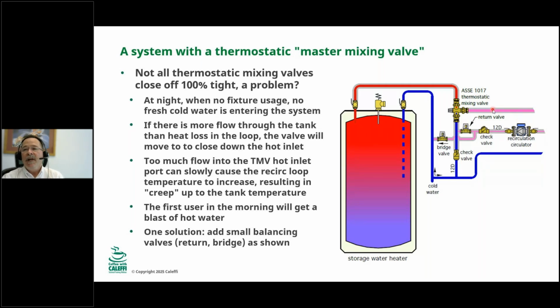On the other hand, if your master mixing valve can close off 100% tight on this hot inlet, like a digital master mixing valve that's a ball valve that can close off tight, you don't have to worry about any of this. Okay, this all goes away. Temperature creep will not happen because the valve can close off completely.